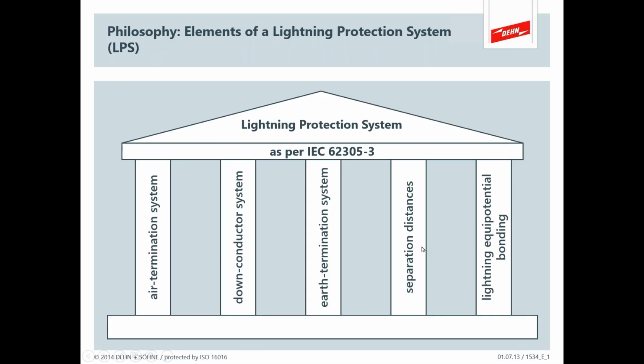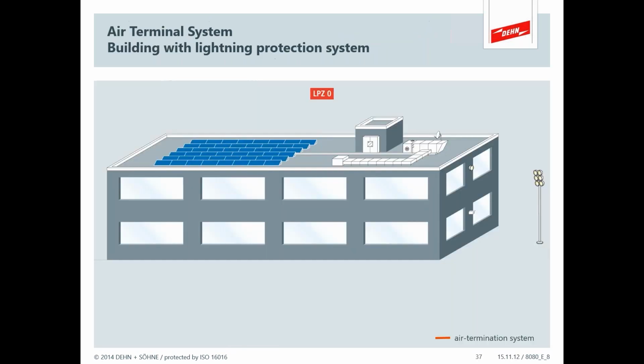And this is why all the factors are important. You can't leave one out and expect not to have problems. So let's look at each one. The air terminal system for a building. And this is a reasonable sketch of the topic. And what's important here is the placement of the terminals are designed to give you, in this case, a rolling sphere solution. So you can strategically pick where to put the terminals and what to use as a lightning conductor.